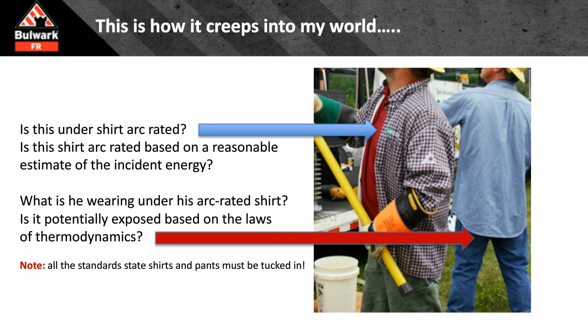It rises. So if my arc flash shoots to the ground, mushrooms, all that hot air comes up, I've now given it a pathway, and if I'm wearing 100% cotton underneath there, which I'm allowed to do, I have fuel that is exposed to hot, hot air and gases. Could it ignite? It takes about 400 degrees to ignite cotton.